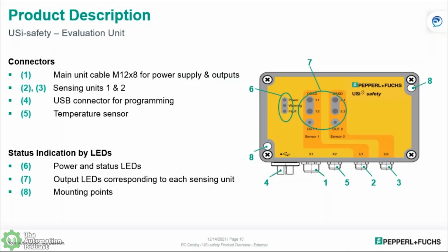We'll just highlight the evaluation unit just a little harder. Like I said, there are two microcontrollers inside of each one of these channels that monitors the sensors, the two transducers. You can use two transducers. You can use one. That's not required for the redundancy. It's just whether or not you need two for your application. And because you have the redundant microcontrollers, the redundant outputs per channel, you do get the EN ISO 13849 for the application for PLd. And like I said, you still get that additional non-safe output for signaling for the warning zone as well.